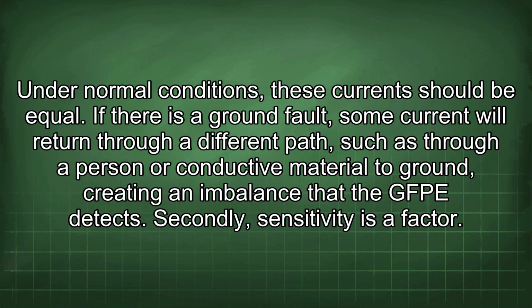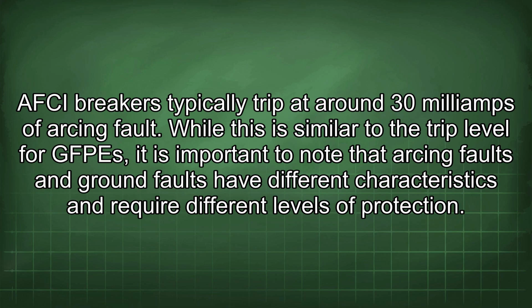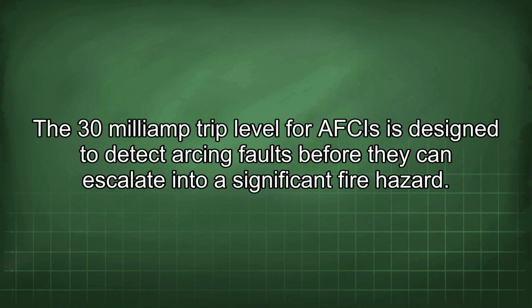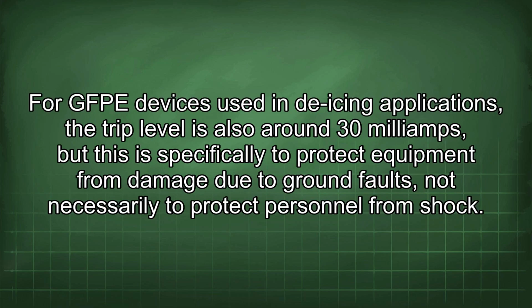Secondly, sensitivity is a factor. AFCI breakers typically trip at around 30 mA of arcing fault. While this is similar to the trip level for GFPEs, it is important to note that arcing faults and ground faults have different characteristics and require different levels of protection. The 30 mA trip level for AFCIs is designed to detect arcing faults before they can escalate into a significant fire hazard. For GFPE devices used in de-icing applications, the trip level is also around 30 mA, but this is specifically to protect equipment from damage due to ground faults, not necessarily to protect personnel from shock.